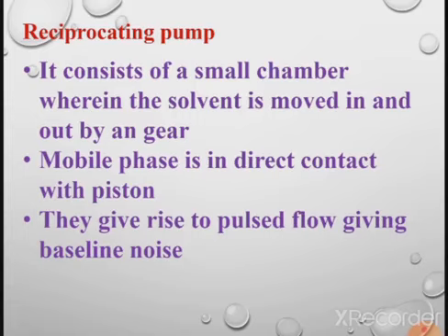Due to the to and fro direction of the piston, the mobile phase is compressed and released, and this gives rise to a pulsated flow, so baseline noise may occur. As well, in this reciprocating pump the mobile phase is in direct contact with the piston, and that's why it may cause corrosion or contamination.